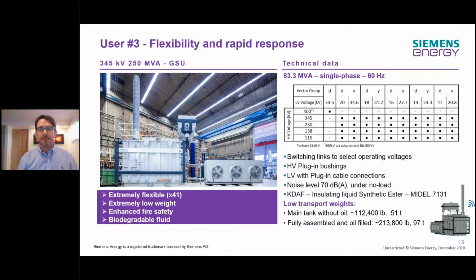And now here, user number 3. I mentioned generator step-up transformers and the challenge of having a lot of different voltage levels that need to be covered if you want to cover a large fleet of generating units. The solution here, we were able to find 41 different voltage level combinations in the low voltage from 12 all the way to 34.5, and on the high voltage from 115 to 400 kV. Extremely lightweight, with enhanced fire safety and using biodegradable fluid as well.